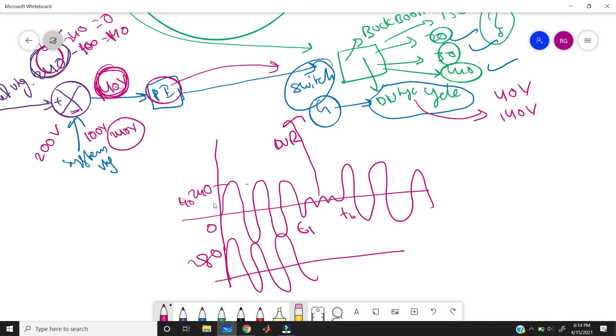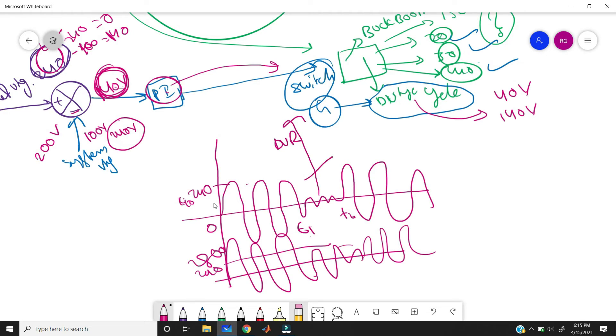We can eliminate voltage sag and voltage swell this way. Looking at the graph, when we are getting less than the rated value, our DVR operates and injects voltage only during the fault interval — from T1 to T2, not from 0 to T1. If we were to inject voltage even from 0 to T1 when the supply is already correct, the load would receive 280 volts instead of 240 volts and the system would become unbalanced. The controller ensures DVR operates only during the fault condition.